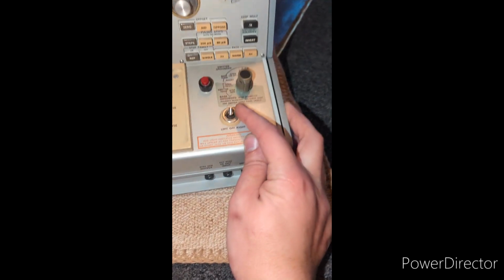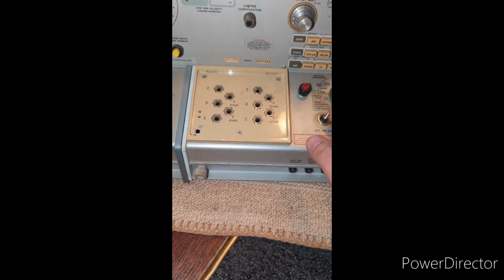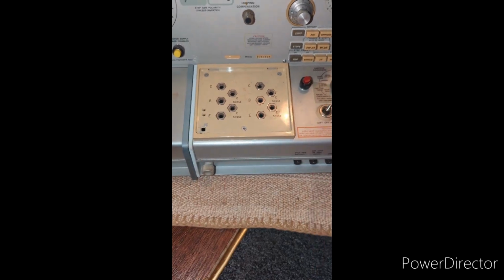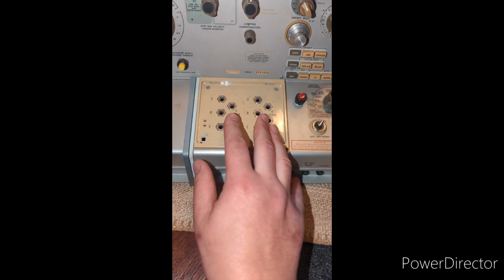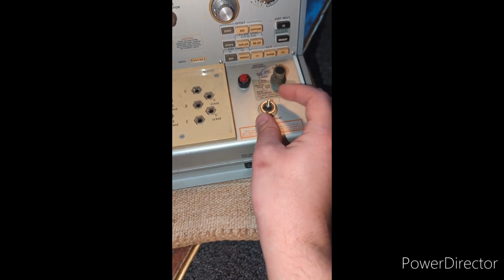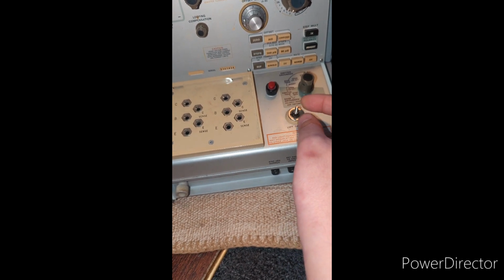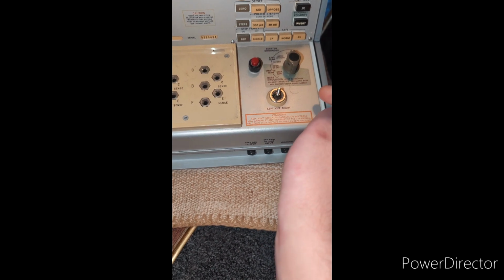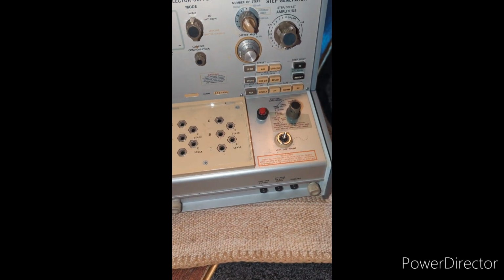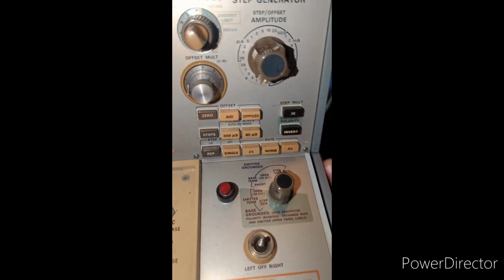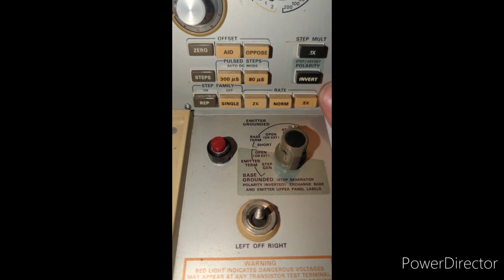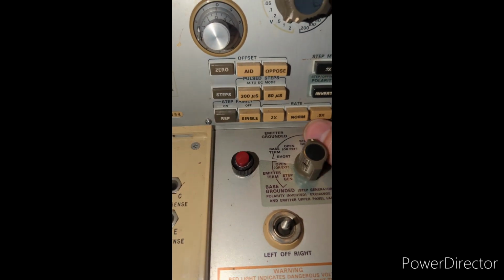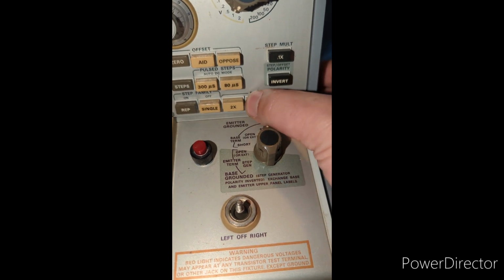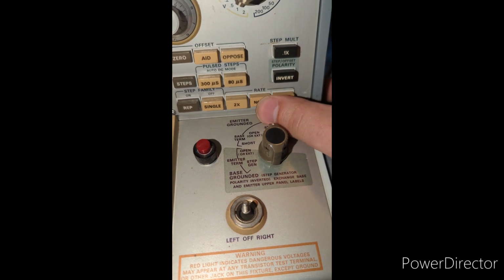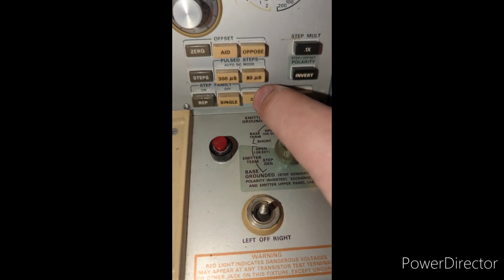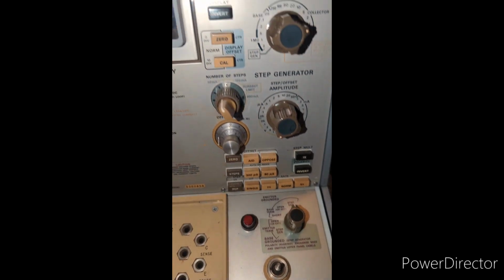Another thing, it looks like the cover for this switch, which toggles between the left and right test fixtures, or in the off position, so you don't have these being live. The cover on this is broke. Not the switch itself, it's just the plastic piece, and actually it was like half there and it came off, so not a huge deal, but that's missing. Let's see. These gang switches down here for setting some of the step generator parameters, they don't stay depressed like this normal switch. So might have some issues here. Let's see.